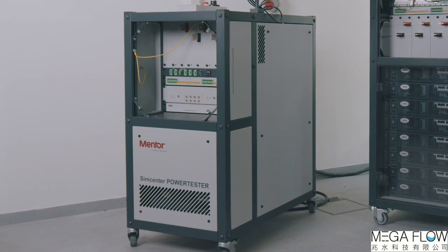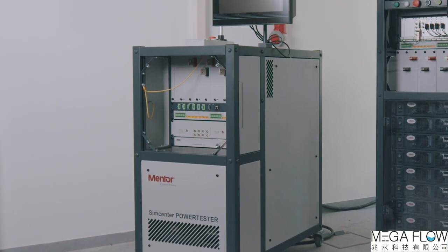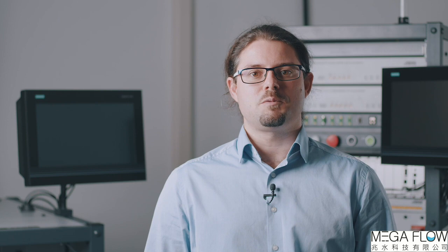This covers the full workflow from the device definition to the actual RTH measurement or power cycling. The system's primary application is testing silicon and silicon carbide diodes, IGBTs and MOSFETs. Let me show you the testing workflow for 16 200 amp IGBT devices.